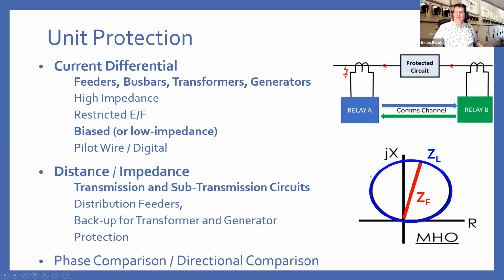And the blue line is the impedance circle of your line in healthy conditions. So if you're inside that line, you've got a fault. If you're outside that line, then you're considered to be healthy for your section. It's predominantly used for transmission and sub-transmission, so that's 132 kV and above. They may also use it for distribution feeders, but it's not that common. And it can be used for backup for transformers and generators because you can set your impedance so that it penetrates into the transformer or the generator windings, usually 50%, the midpoint of your transformer.